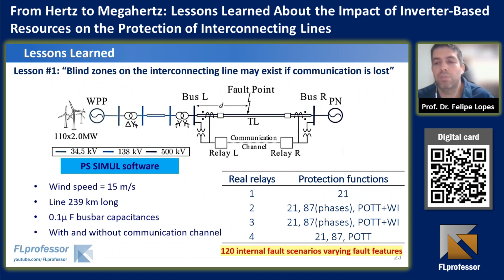This is a very long line, in my opinion. We considered some busbar capacitances, which will be addressed soon in this presentation. And two scenarios were taken into account. The first one is with a communication channel, and the second one without a communication channel. And four real relays from different manufacturers were taken into account, considering distance protection, phase elements of the available differential protection, pilot schemes, and whenever the weak infeed logic was available, we activated it. It resulted in 120 internal fault scenarios in which we varied the fault features.